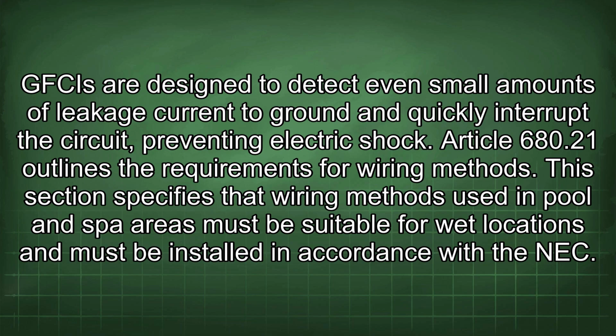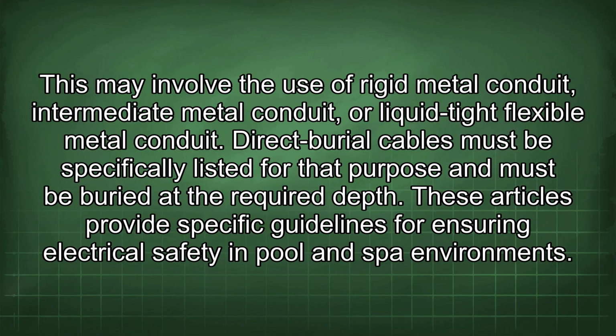Article 680.21 outlines the requirements for wiring methods. This section specifies that wiring methods used in pool and spa areas must be suitable for wet locations and must be installed in accordance with the NEC. This may involve the use of rigid metal conduit, intermediate metal conduit, or liquid-tight flexible metal conduit. Direct burial cables must be specifically listed for that purpose and must be buried at the required depth.